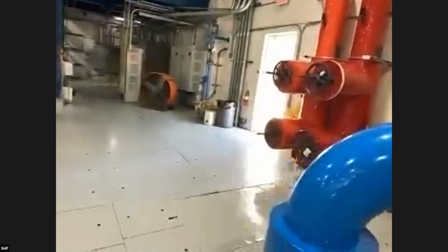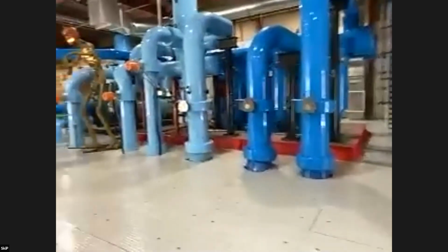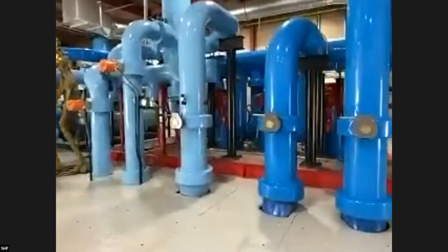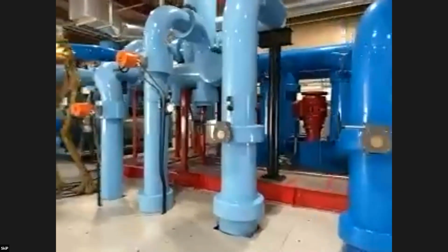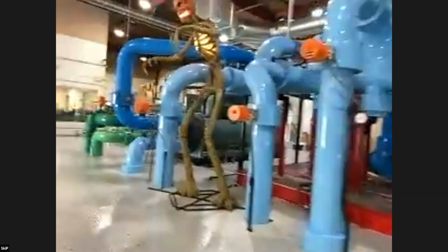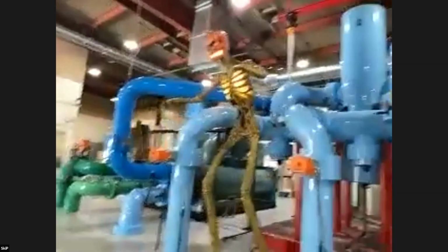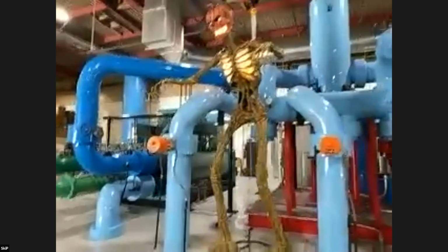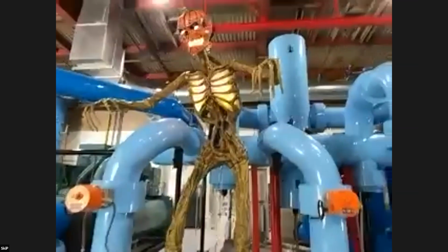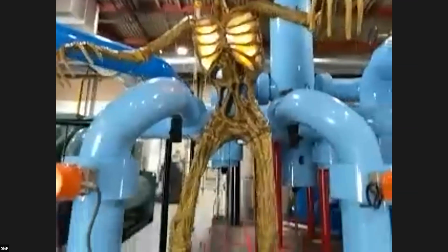It goes through all the air handlers or the radiators, and then we blow cold air into all the different spaces. Then we bring back warmer water, usually about 12 to 13 degrees warmer. So if we send it out at 40 degrees, it comes back at 52, 53 degrees, and then we cool it back down and start the cycle all over again.